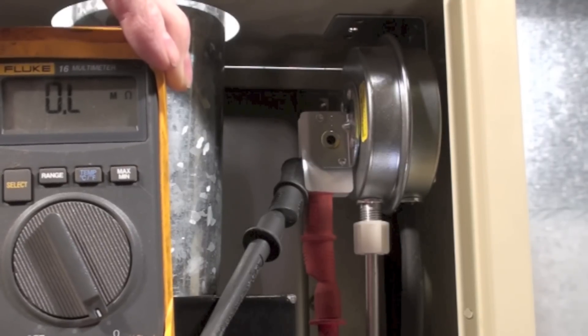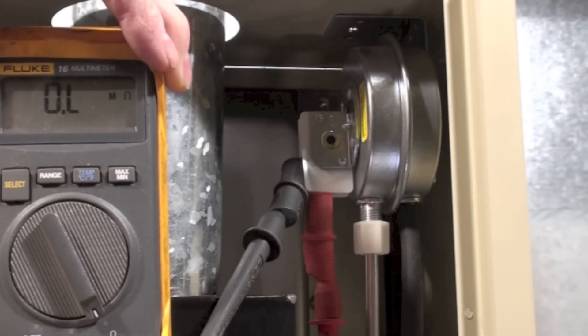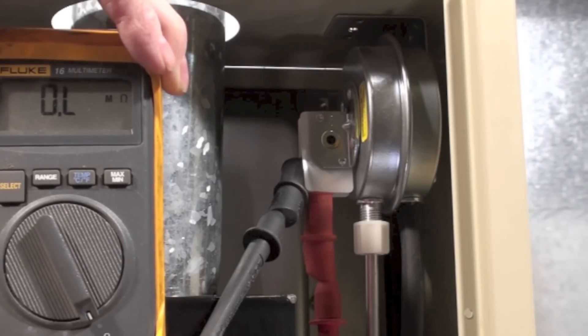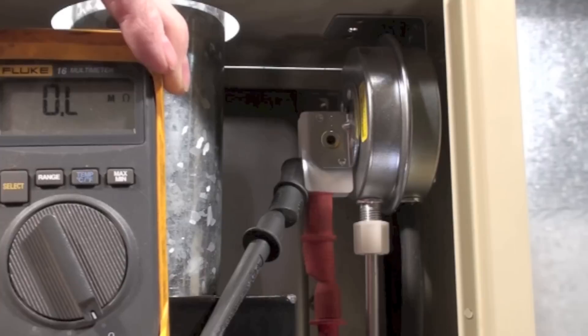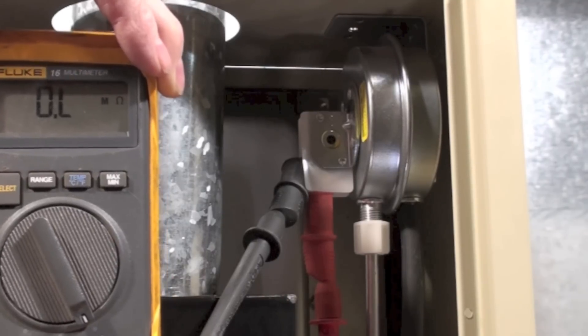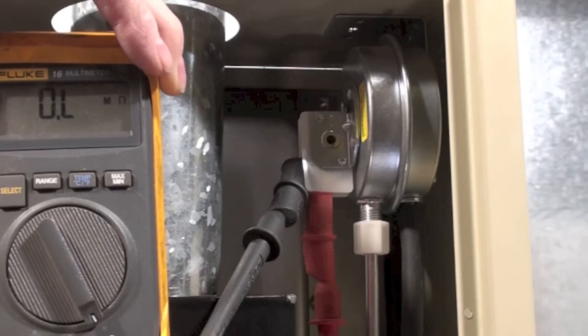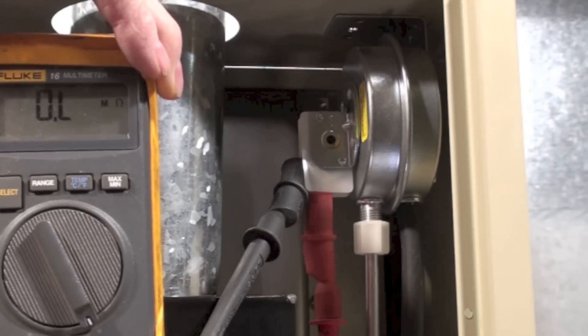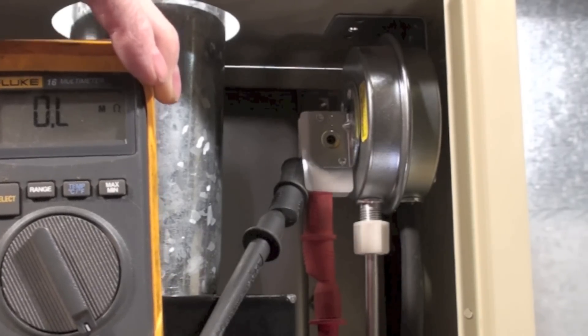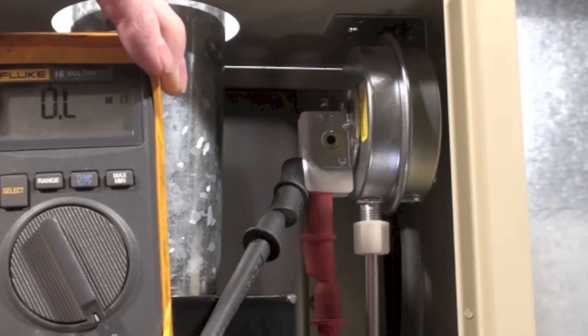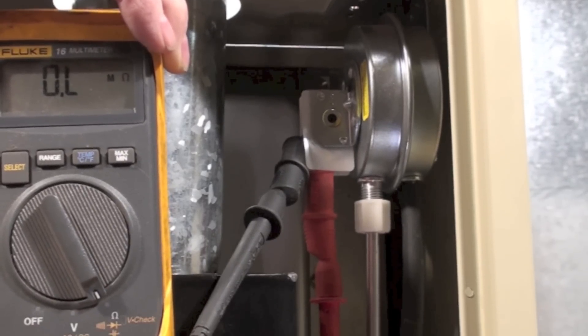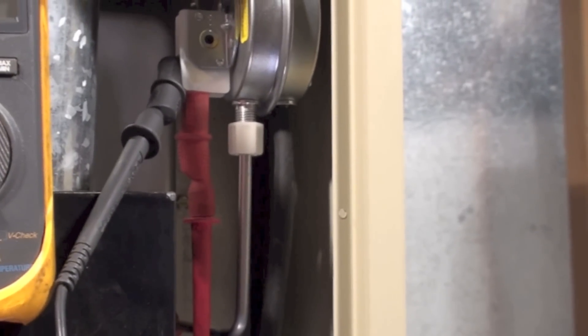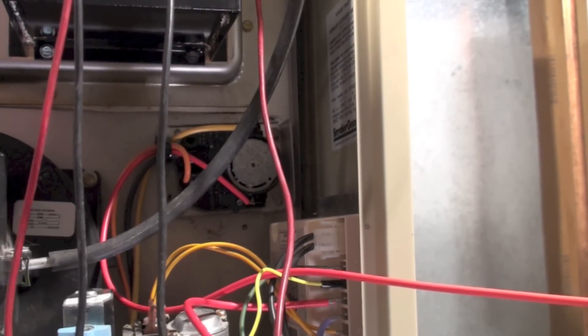then the next thing is you've got to start looking at the switches in series with it. Once that inducer comes on, or in this case forced draft blower, once that forced draft blower comes on, you know it's on, it's ready to go, there's power to start it. And then it could be the centrifugal switch inside the combustion blower that's right there, or it could be the pressure switch, and it could be that limit switch that's kicked off there.